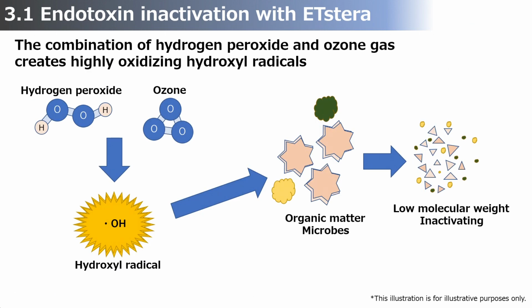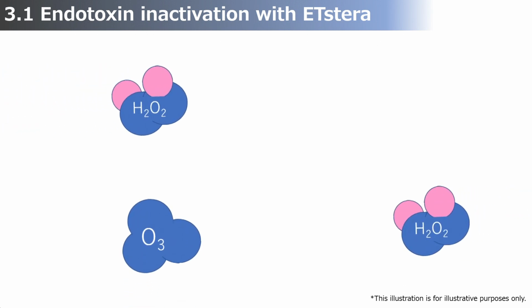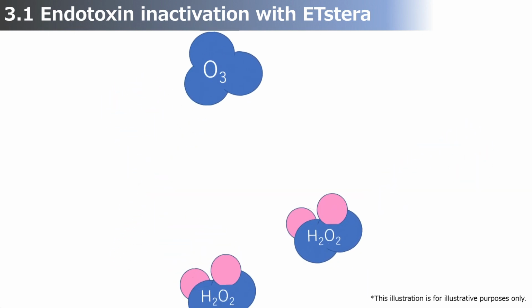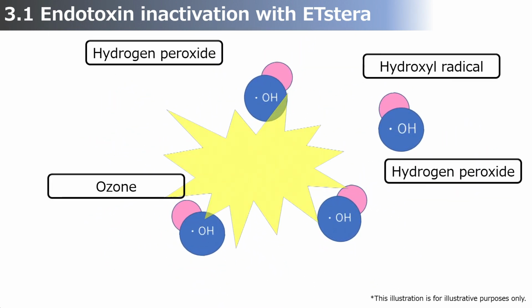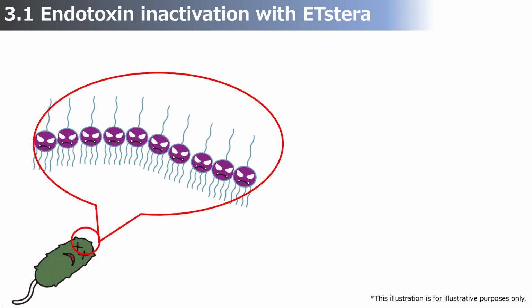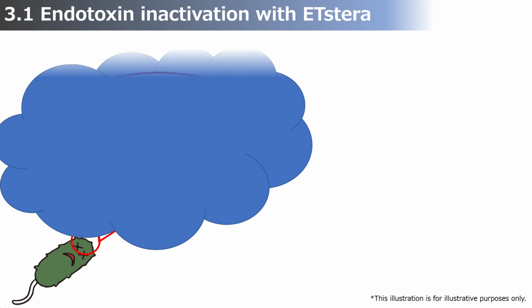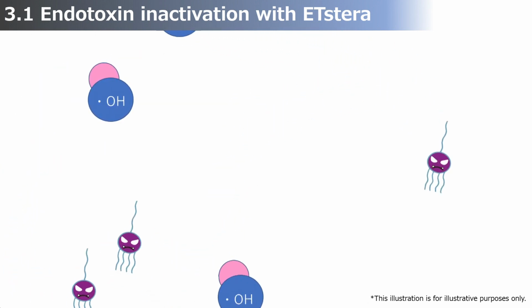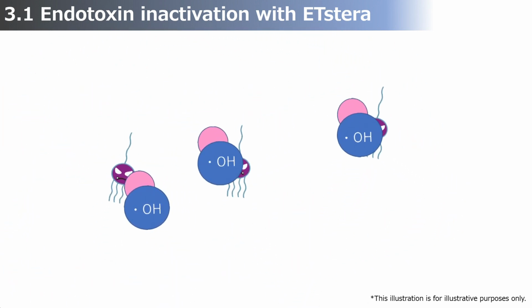Rather than using only hydrogen peroxide gas or ozone gas, ETstera combines the two to promote accelerated oxidation and improve sterilization. Combining hydrogen peroxide with ozone is an efficient way of generating hydroxyl radicals, which are strongly oxidizing and are the most active of all the molecules known as reactive oxygen. Hydroxyl radicals are strongly oxidizing, and the reactive oxygen they contain is effective in breaking down endotoxins.